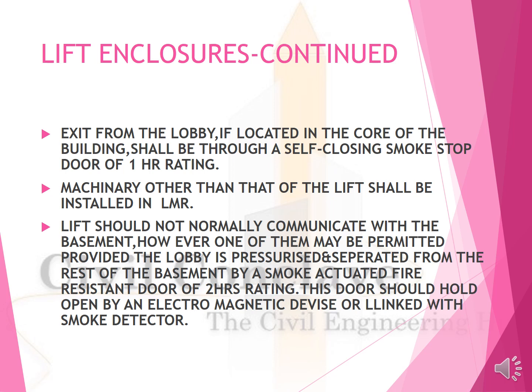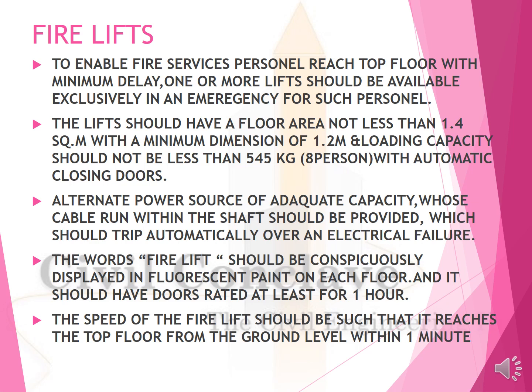Lifts should not normally communicate with the basement. However, one of them may be permitted provided the lobby is pressurized and separated from the rest of the basement. The door should be held open by an electromagnetic device or linked with a smoke detector. To enable service personnel to reach the top floor, one or more lifts should be available exclusively for the fire personnel. The lift should have a floor area not less than 1.4 square meter with a minimum dimension of 1.2 meter and a loading capacity of 545 kgs.